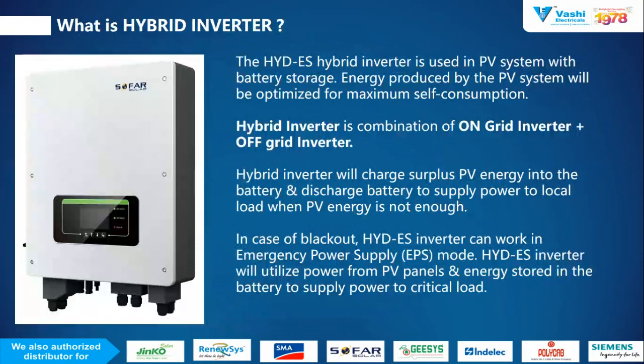Now our main topic of this presentation is the hybrid inverter. So what is the hybrid inverter? It is a combination of on-grid plus off-grid inverters. It will use the power from PV to charge the battery and discharge the battery to drive your home load when PV voltage is not available. It means whenever your electricity is not available, it works as an off-grid inverter, and during the daytime when PV and grid are both available, it works as an on-grid inverter. So in case of blackout time, blackout means unavailability of grid power and PV power, both.